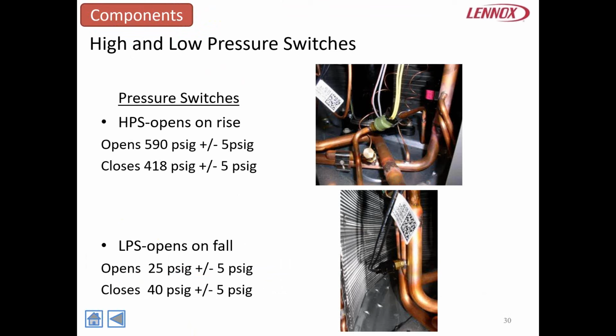Okay, so one thing I want you to be aware of is if it trips 5 times and locks out, it's not a nuisance trip, it's not a shadow. There's something going on. So many times I have technicians that have been out 2 or 3 times and they've had a 590 psi lockout, and they change the board, they change the sensor, they come back, and it's still doing it. They hook their gauges on, and at that time that they're there, they're just running 250, 260 pounds of pressure on the high side, and the low side looks within range. So it's doing something when they're not there, right? And that's why the switches are there to protect the unit when you're not there to monitor it 24/7.